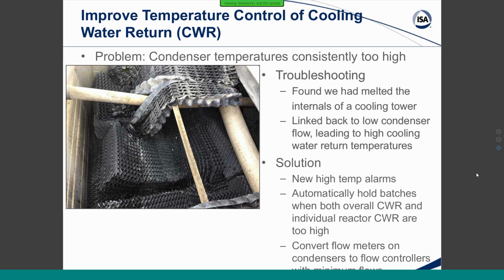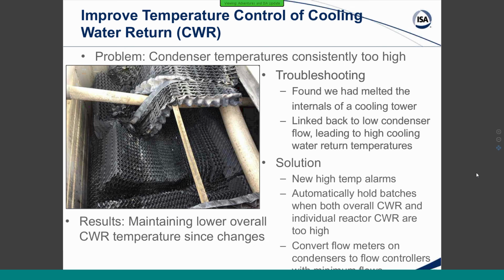We also put some new, appropriately justified alarms on our cooling water return temperatures. We programmed logic that would put batches into held if both the individual reactor cooling water return temperature and the overall cooling water temperature were above a safe point, as we decided. And we did spend some money. We took all of the flow meters that we had on our condensers and changed those over to flow controllers. With the flow controllers, we were able to put a minimum flow rate on there that would keep us in a safer temperature region. So results were also good on this one. We haven't done any further damage to the towers, and we've been maintaining lower overall cooling water return temperatures.